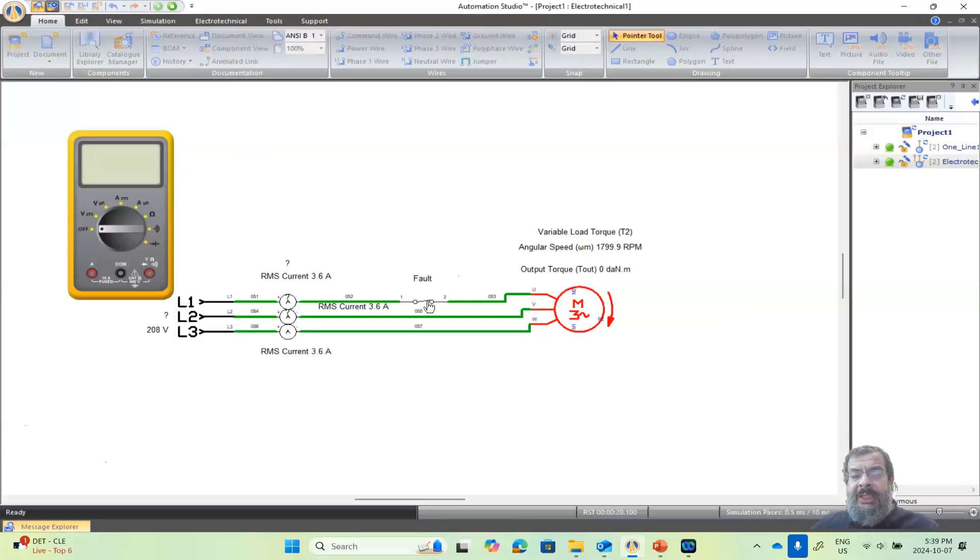Now let's see what will happen if I disconnect one of the phases, meaning a fault happened here. Look at the currents here: the current becomes high, low, high—high currents. And look at the speed here and the torque. You start to have a pulsating system or pulsating torque.